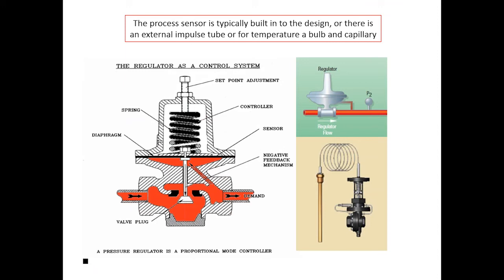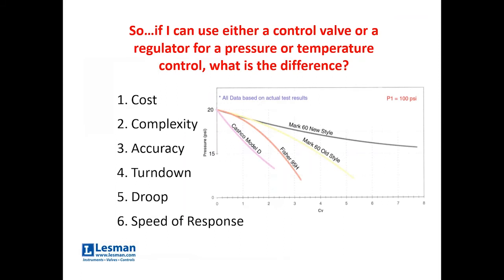If you look up to the right, there's two other examples of how it could happen. There's that little green box, there's a pressure regulator with an external piece of tubing going out and tapping into the downstream pipe. So, that's where it's picking up the process variable, in this case, pressure. In the tan box below it, we go back to a temperature unit with the classic capillary. So, the question on the slide: if you can use either a control valve or a regulator for pressure or temperature control, what's the difference?